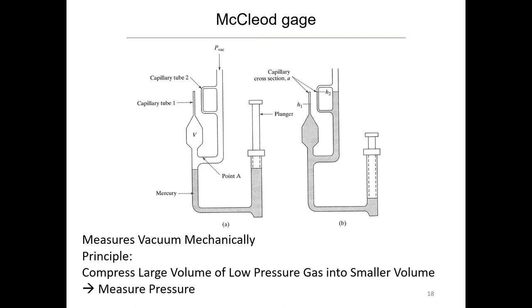We're going to study three devices. The first one is the McLeod gauge, shown here in two states: state A and state B. It measures vacuum mechanically. The principle is it compresses a large volume of low-pressure gas into a smaller volume, and through that compression you measure the pressure. We'll walk through how the device works on the next slide.